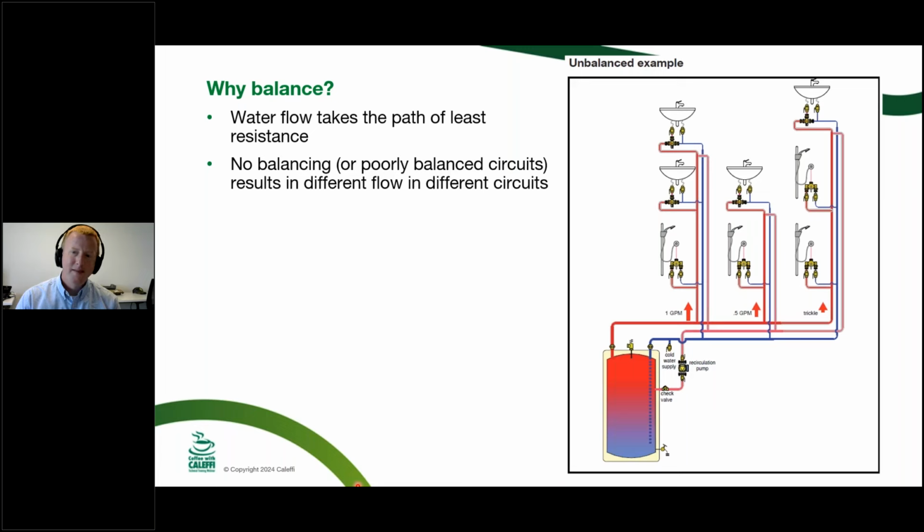But the problem is that you're talking about buildings that are set up exactly the same way across all the risers and everything like that. And that would be probably pretty great, but if you've got buildings that vary in height or length or anything like that, as far as how these recirc runs are going, reverse return might not be your best choice there.